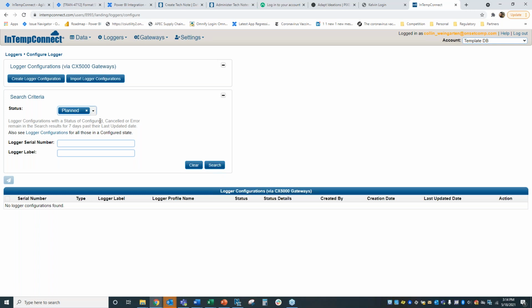As a requirement for VFC, we have to record low and high temperatures. How do we clear them? The only way right now is to perform a download and restart, which the gateway will do every week, or you can set it to do every day. You'll just have to put 7 days of daily reports together when you submit it to the CDC.